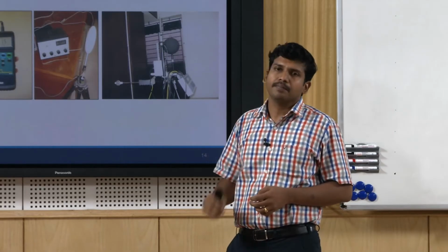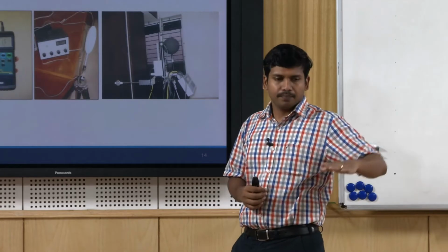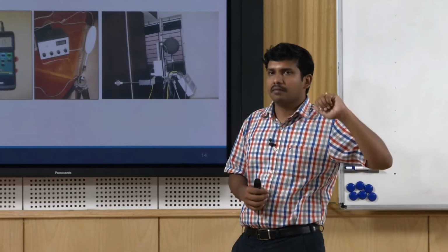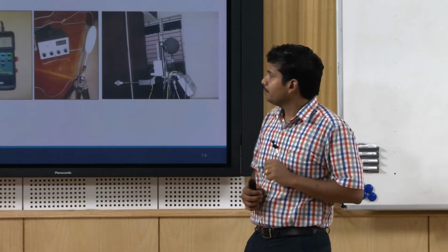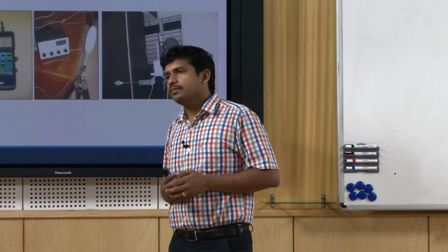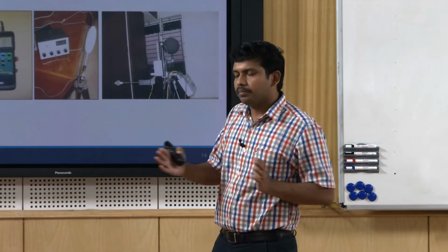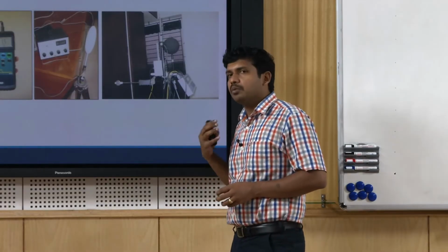Then comes the level 1 survey, where the temperature, humidity as well as the thermal environment are recorded at 3 different levels. Say if a person is seated, you take it at the foot level, the waist level as well as the head level, and the same for a standing person. Apart from this, it also needs a continuous recording for at least a duration, so that you measure the thermal environment around him for a particular duration. It is not like a momentary survey.